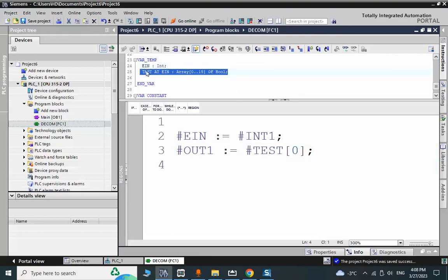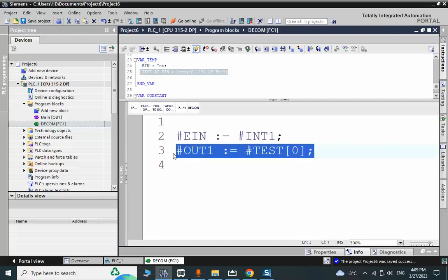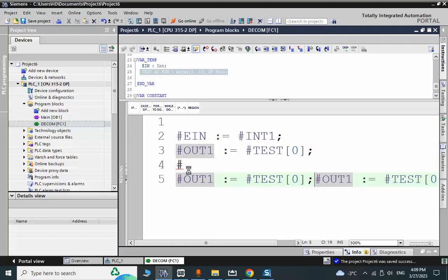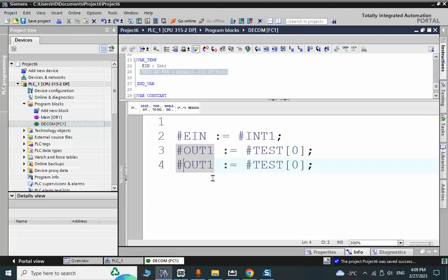By using this syntax, the copy of 'integer one' is placed into 'IN', and 'IN' is also split into an array of 16 boolean elements. We then copy each element to one output — so output1 gets TEST[0], output2 gets TEST[1], and so on.